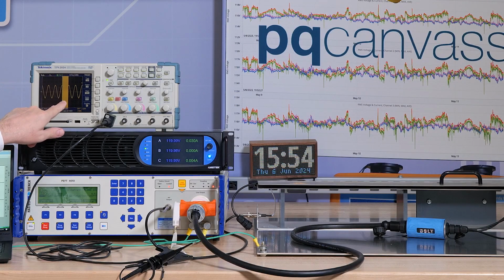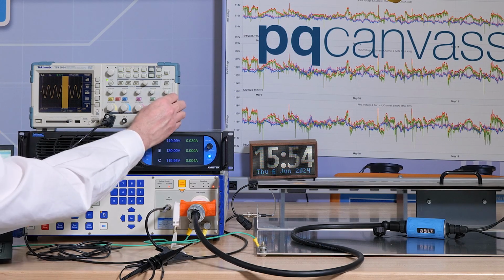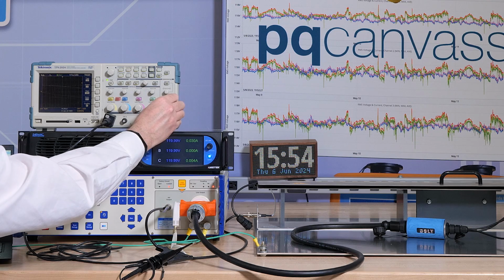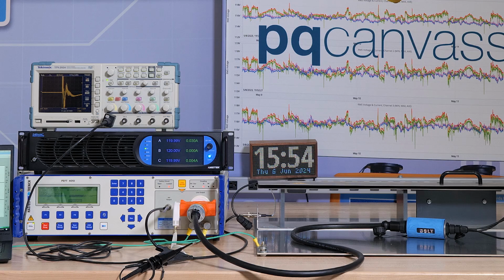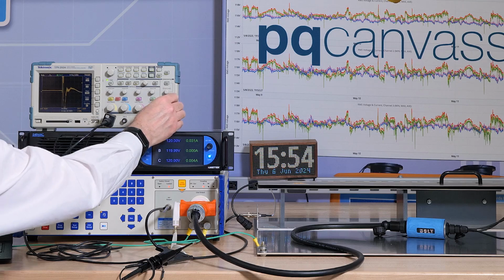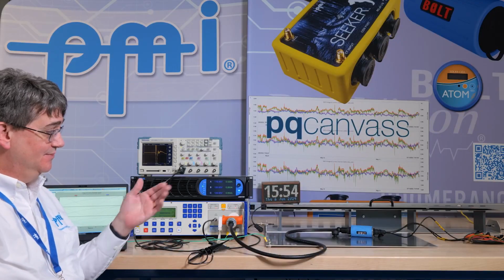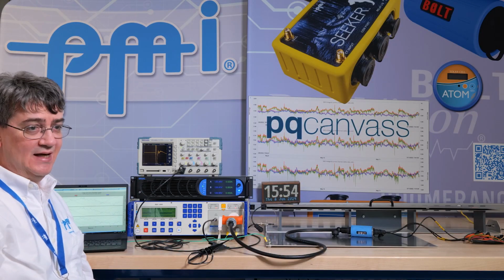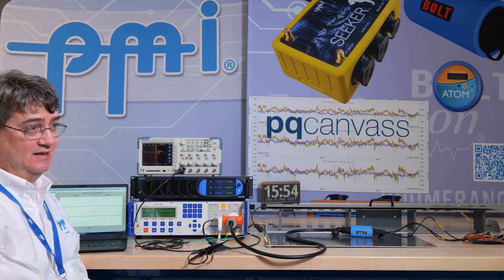You can see the 15 millisecond pulses, they're much larger than the 120 volt sine wave, and if we zoom in, we can see that these are extremely narrow. They're 5 nanosecond wide rise time, 50 nanosecond duration. So those are 1,000 times faster than a single sample on the bolt. So it's very high frequency pulses that are way outside the power quality realm.